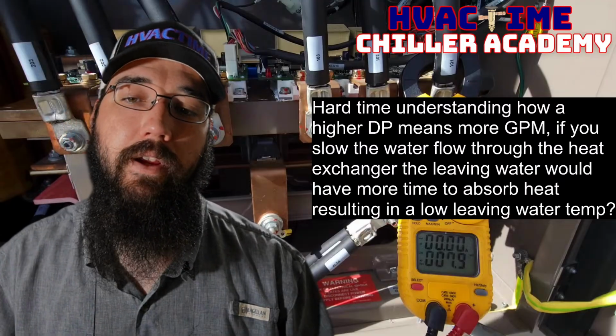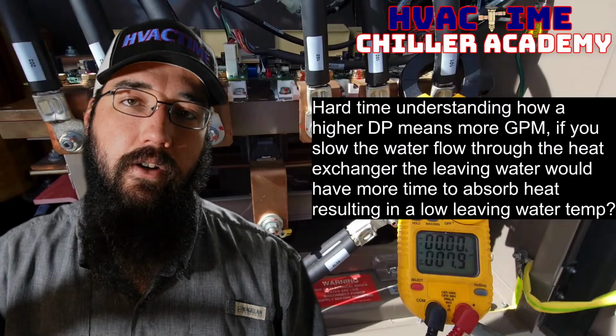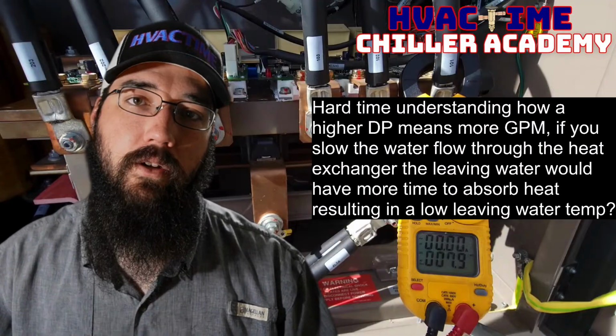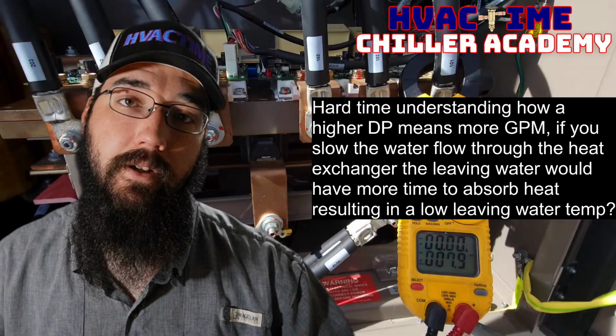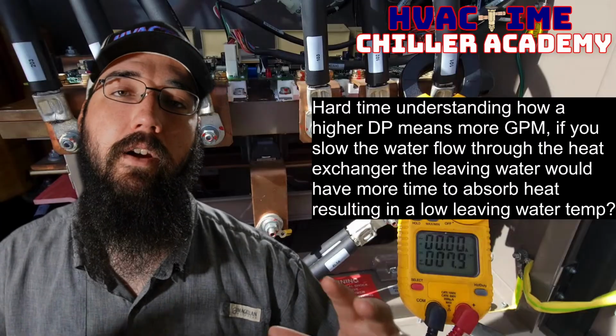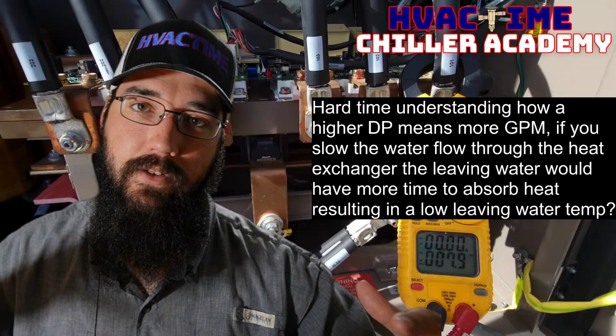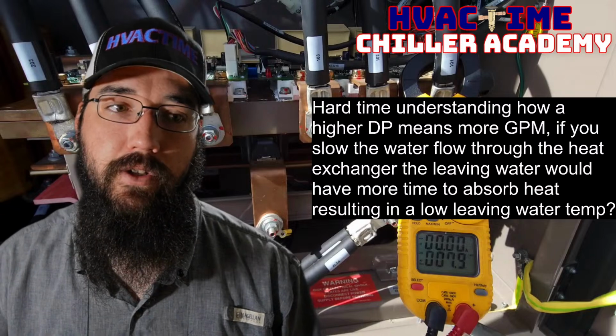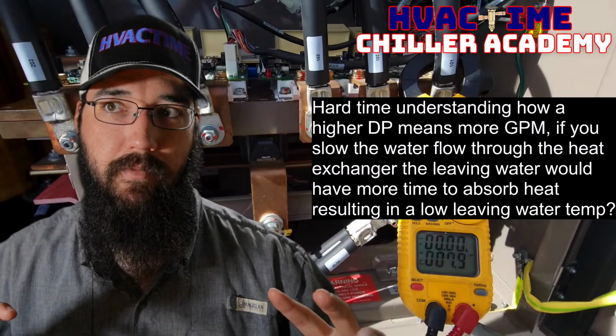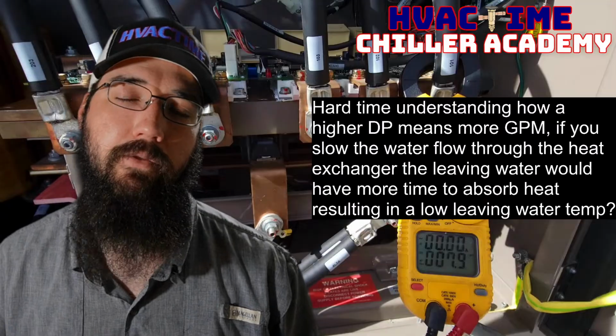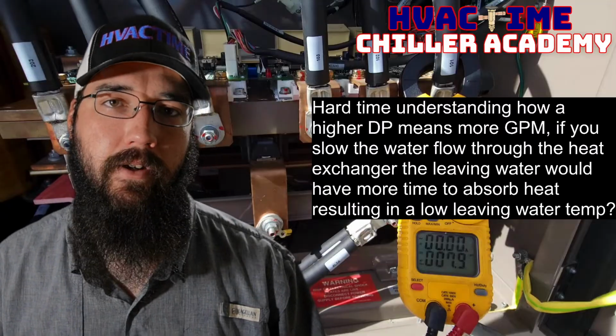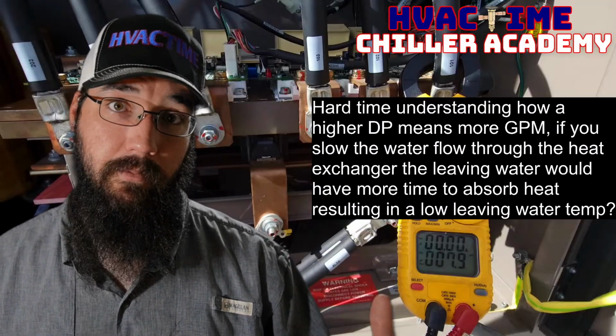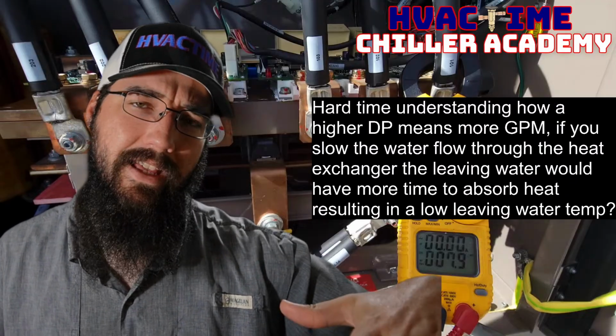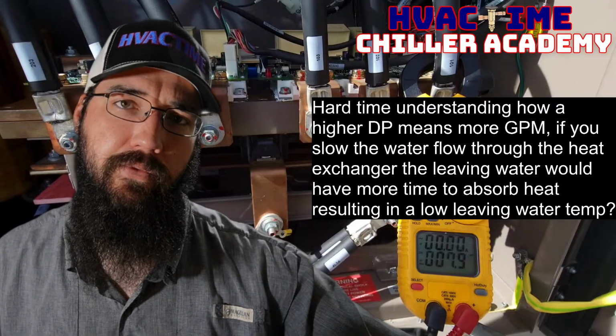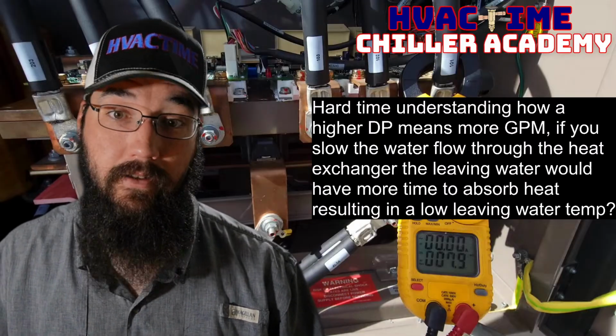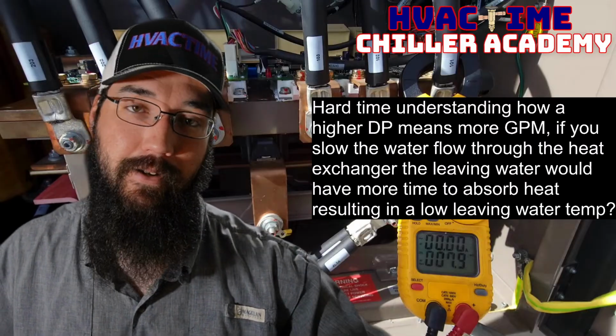So to your point, yes, if we are lowering GPM, we will make leaving water set point, or we will get colder leaving water easier. And if we're raising GPM, it will be harder to achieve that. And the goal is to hit the correct, call it sweet spot, if you will, the design point in the middle there. Because that is a symptom that we can have. We can, in some cases, force so much flow if a plant's that badly designed, and like I've come across them.